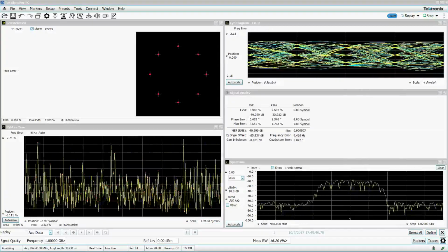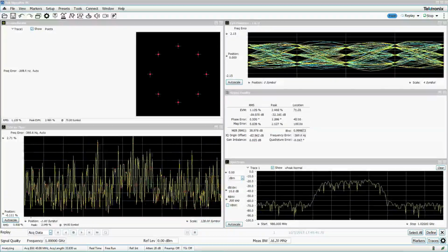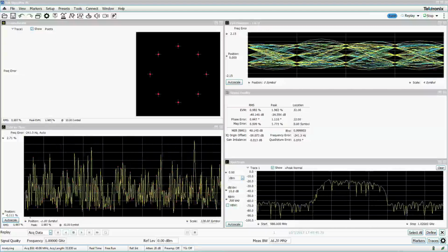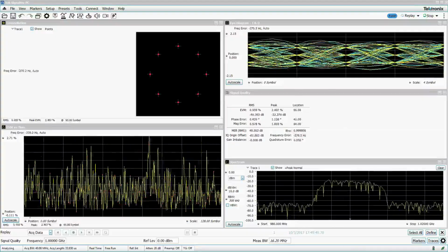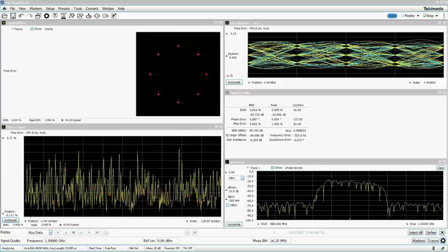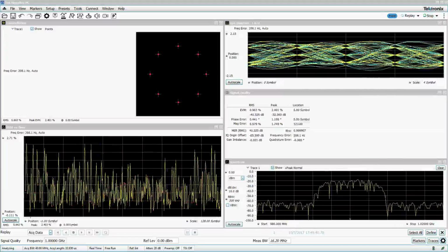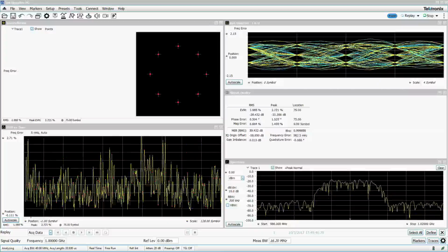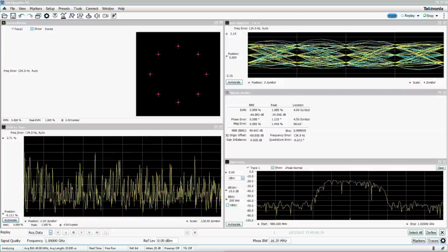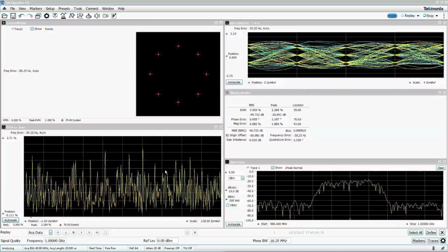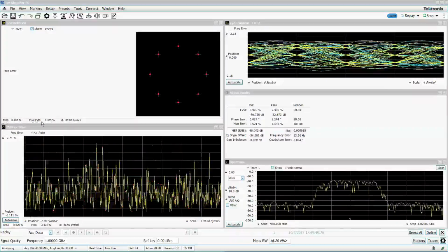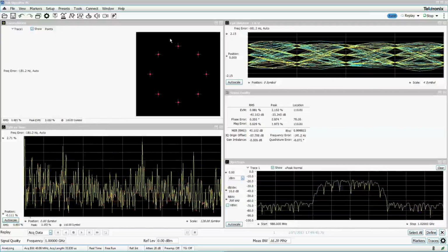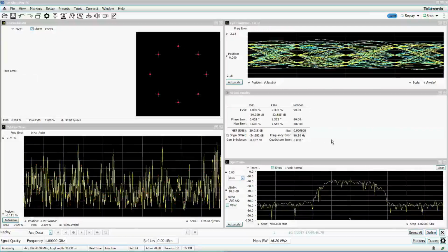Today we're going to discuss digital demodulation. Although these concepts are common to almost any vector signal analyzer that provides digital demodulation capabilities, I'll be demonstrating using SignalVu-PC and the RSA-507A. Digital demodulation is valuable for those who need to validate or characterize the quality of a digital communication channel.